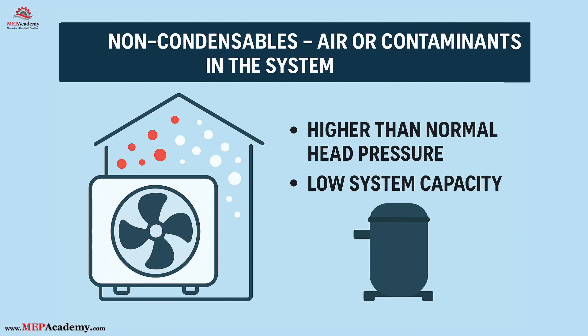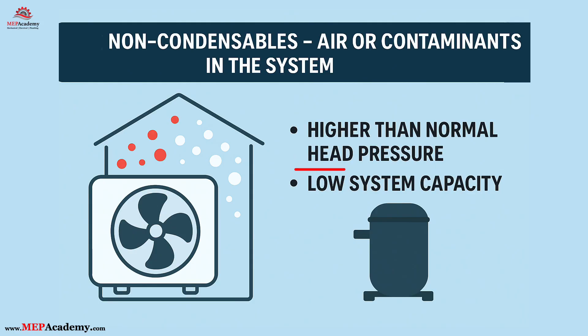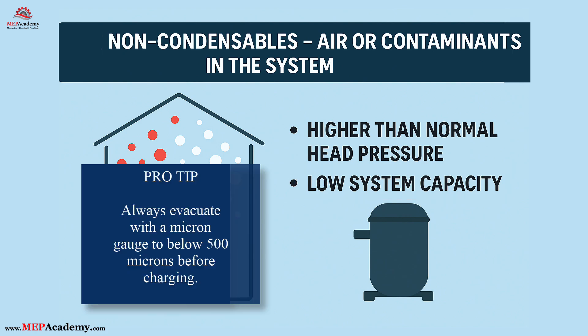Number five: non-condensibles — air or contaminants in the system. Air or non-condensible gases can be accidentally introduced during poor evacuation or improper charging, leading to high head pressure and poor heat rejection at the condenser. Non-condensibles like air or nitrogen do not condense in the condenser, so they take up space and reduce heat transfer efficiency, causing head pressure to rise and reducing system capacity. Pro tip: always evacuate with a micron gauge to below 500 microns before charging.